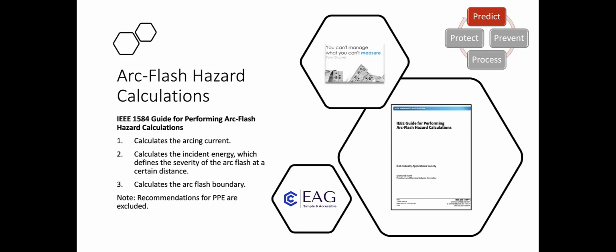So on the second point, it calculates the incident energy, which defines the severity of the arc flash at a certain distance. The true SI unit is joules per square centimetre, although it's popularly expressed in calories per square centimetre. 1.2 calories then per square centimetre, or the true SI unit, 5 joules per square centimetre applied to the skin for 1 second is a threshold at which there could be an onset of a 2nd degree burn. And this figure then is used in determining the PPE requirements and the arc flash boundary, which I'll mention as well. So lastly, an arc flash boundary can be calculated. It's where the incident energy is reduced to its key number of 1.2 calories per square centimetre. So again, I'll mention that again.